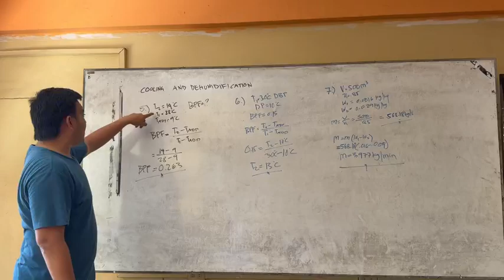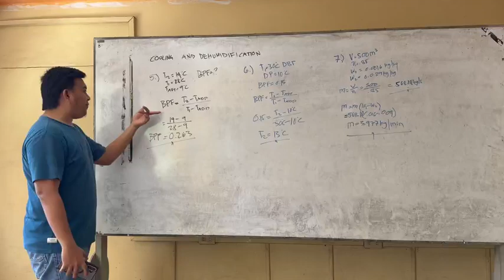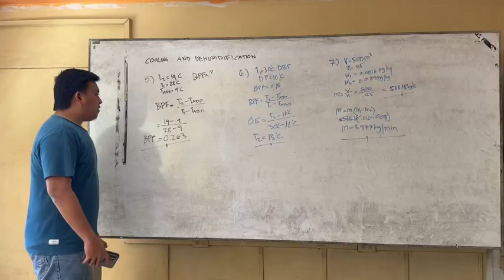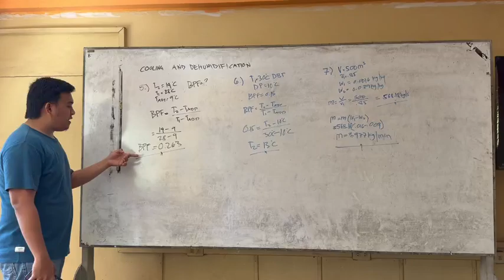We have the following values: temperature 1, temperature 2, and the apparatus dew point temperature. The formula for bypass factor is (temperature 2 minus apparatus dew point) over (temperature 1 minus apparatus dew point). By substituting all the values, we get the answer of 0.263. So the bypass factor is 0.263.